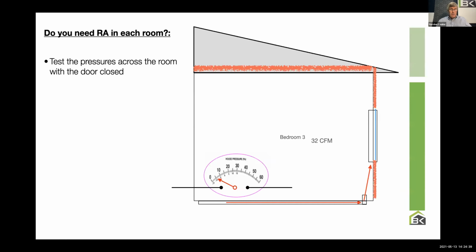The next question I get is, what about return air? Would it help me if I had return air in that bedroom? And the answer is, test the pressure across the room with the door closed and the door open. If the pressure changes by more than 3 to 5 pascals, then you need return air. Otherwise, you don't. And here's why I can say that with a high degree of assurance. How much air did we need to heat that room? Let's call it 40 CFM. How much heat do I get by taking air out of that room? And the answer is none. If I take out 70-degree air and bring in 70-degree air, I didn't add any heat to that room. Return air does not help you heat or cool a room.